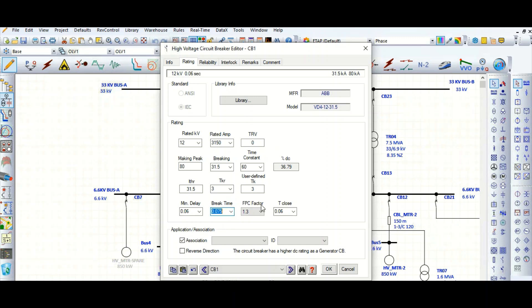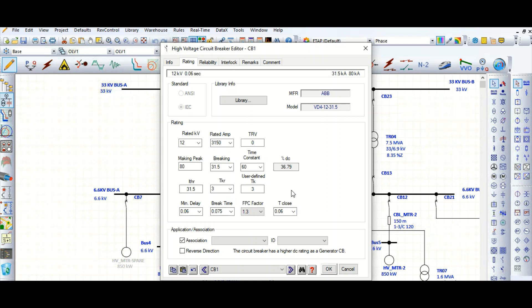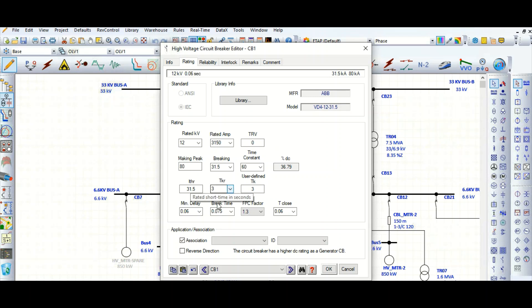This is the first pole to clear factor — by default it is 1.3. And this is the rated closing time: 0.06 seconds, meaning 60 milliseconds. So the main parameters are: rated kV, rated amps, peak current, breaking and thermal withstand current capability in kA rms, duration in seconds, minimum delay, and break time. These are the main parameters of a high voltage circuit breaker.